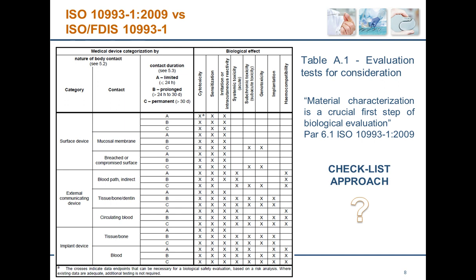Many of you are familiar with the approach set by the current ISO 10993-1. In the majority of cases, the table provided in Annex A is used as a checklist, with all the biological effects evaluated by means of in vitro and in vivo tests. In reality, the standard says that those tests are not mandatory and that material characterization is a crucial first step of the biological evaluation.